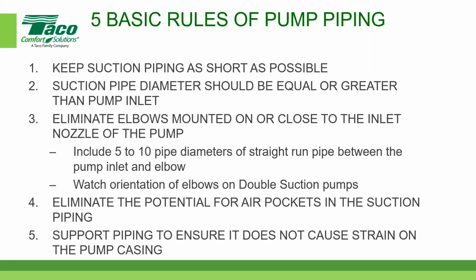And then you've got that old 5 to 10 pipe diameters, or maybe a suction diffuser instead. And I'll show you a picture shortly of what we're talking about there. That's another pump product that you can get from your manufacturer's rep, and we all sell them. And it really allows you to not have to use that 5 to 10 pipe diameters to get good flow going into the pump.